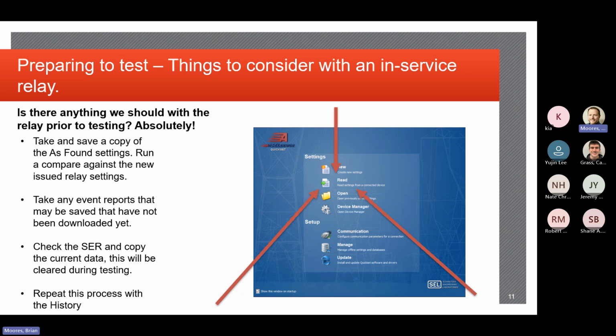where someone went to a relay, made changes to the relay, and it caused a trip. It was a Cooper relay or something, and instead of read and send settings, it was upload and download. Upload and download can mean two different things depending on whether it's referring to the relay or the computer you're connecting into, and it was opposite of what your instinct would say. So instead of reading settings, they sent default settings, which resulted in a lower current pickup. Once those settings got loaded and saved, the relay determined an overcurrent and tripped. The problem is they didn't have the settings to put back in the relay, so there was a big scramble.